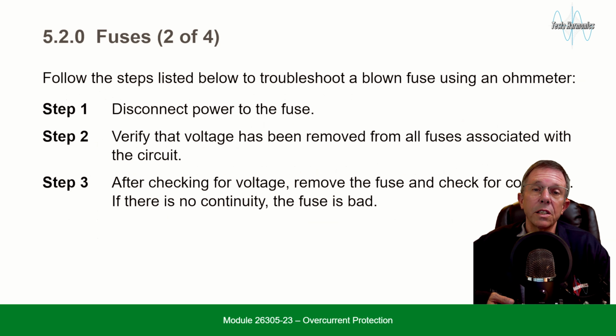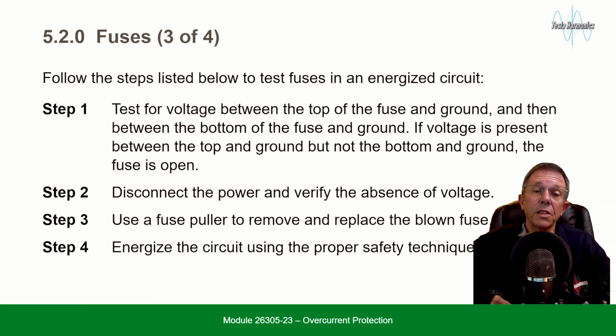Follow the steps listed below to troubleshoot a blown fuse using an ohm meter. Step 1. Disconnect the power to the fuse. Step 2. Verify the voltage has been removed from all fuses associated with the circuit. And Step 3. After checking the voltage, remove the fuse and check for continuity. If there is no continuity, the fuse is bad.